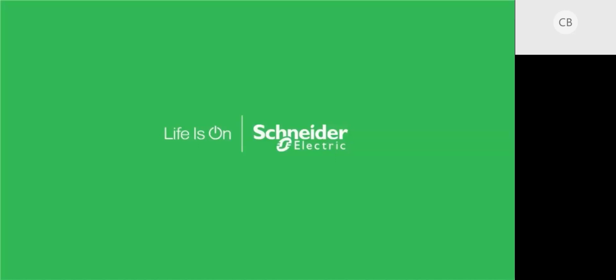Okay. Next question, can UPS plus lithium ion be used as peak shaving with old UPS equipment, or do you need to replace the old UPS to get all the benefits? Yeah, so that's specific to a Schneider solution for newer UPS systems. It requires a software upgrade or a firmware upgrade so that it can interface with our Microgrid Advisor software solution and make intelligent decisions about when to go onto batteries to do some peak shaving. So it's not retroactive back to anybody's UPS system or older Schneider UPS systems. To be very specific, it's the Galaxy VM and the Galaxy VX currently, and somewhere in the future it will also be the Galaxy VS, the smaller one.